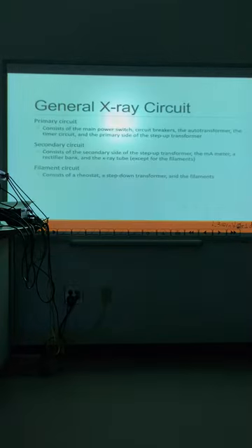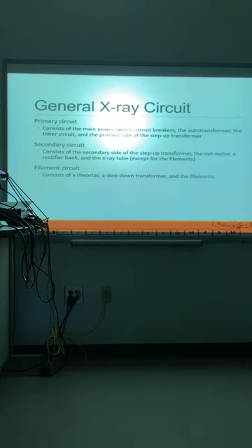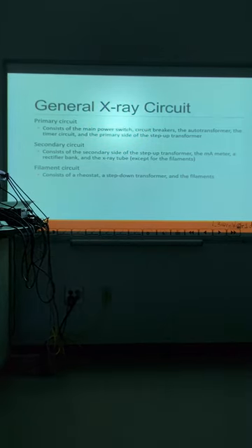But I need to make sure y'all understand that the primary circuit consists of the main power switch, the circuit breaker, the auto transformer, the timer circuit, and the primary side of the step up.